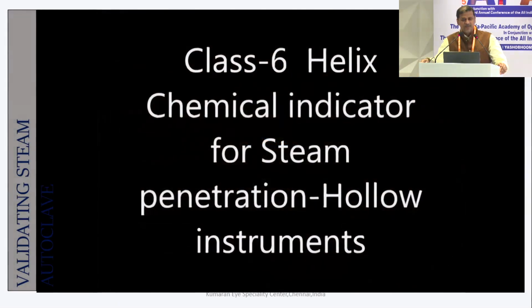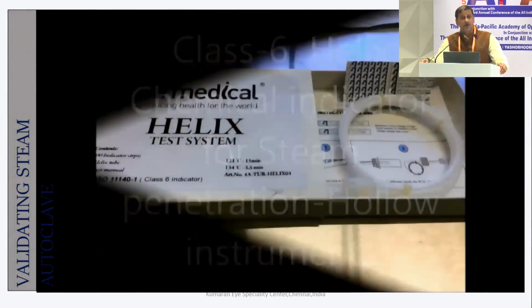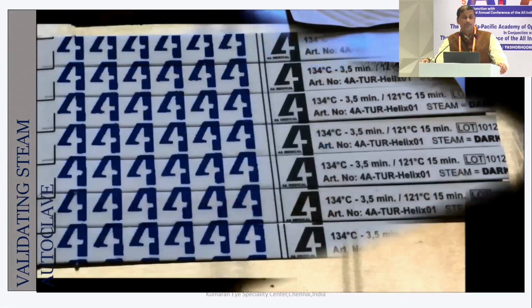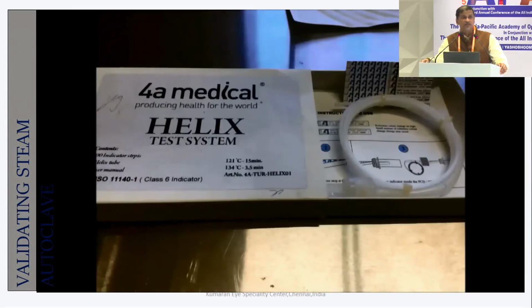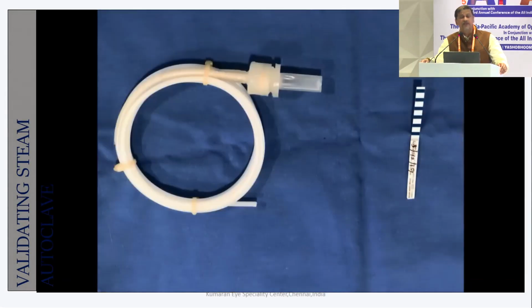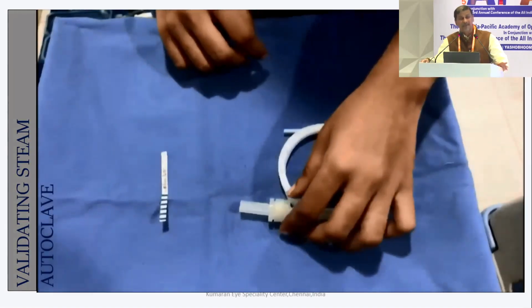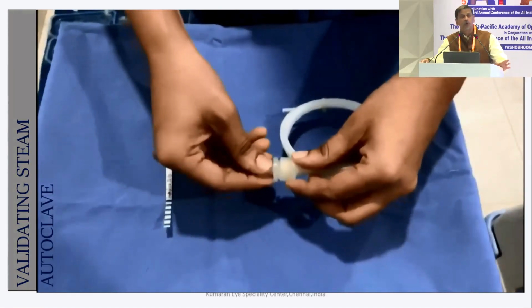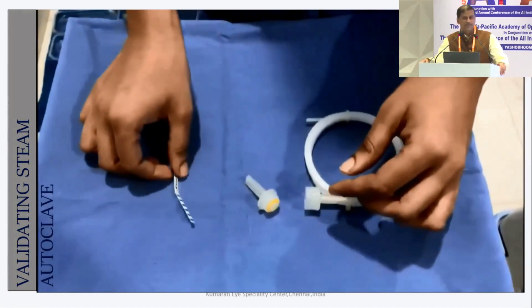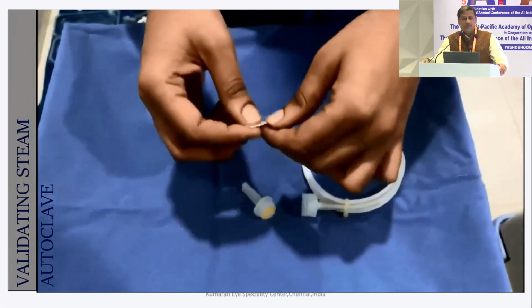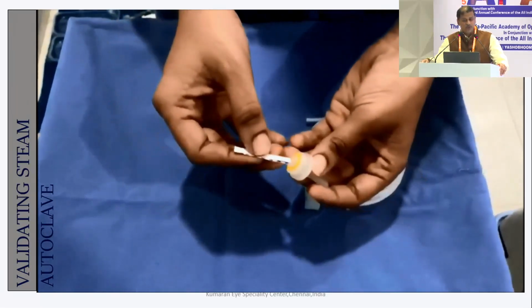The next one is the class 6 autoclave indicator, which is otherwise called the PCD, the process challenge device. So what is the process we're going to challenge? That is the ability of the autoclave to make the steam go inside a hollow tube, because we do have tubings, right? So this is a 1 meter long tube, available in silicone or stainless steel.